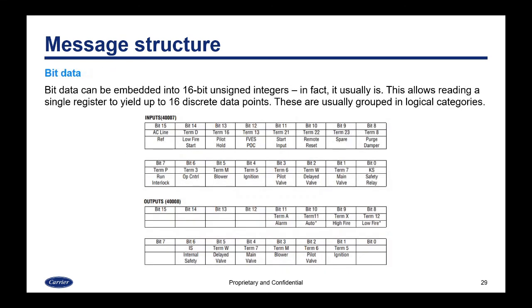Bit data can also be embedded into 16-bit unsigned integers, and in fact this is usually how it's presented. Bit data allows reading a single register of on or off values, and you can yield up to 16 discrete data points by putting them into one 16-bit unsigned integer. They are usually grouped into logical categories — so in one example, one register will group inputs and another will group outputs, and depending on which bit is on, it will tell you if an input or output is on.